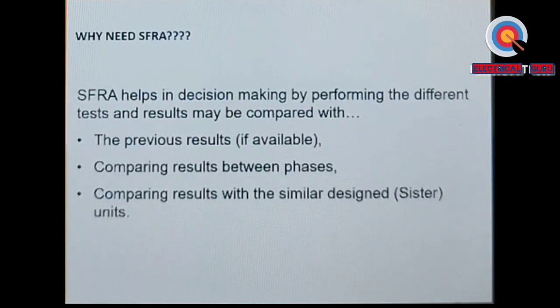Or comparing results with similar design units. Say the transformer suffered a major failure and all 3 phases have suffered some damage, and you don't have any reference. Then what we suggest is, same manufacturer, similar design, you test that transformer, so that gives you a reference signature, and with that you can compare whether the transformer which has suffered some fault has developed some permanent damage.